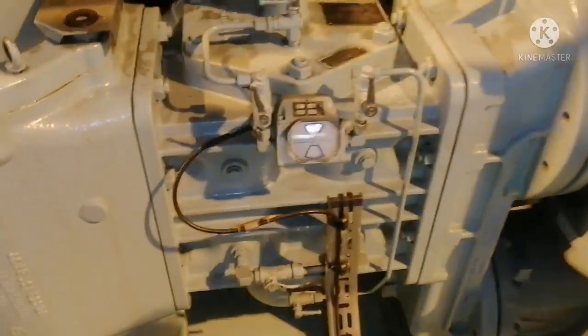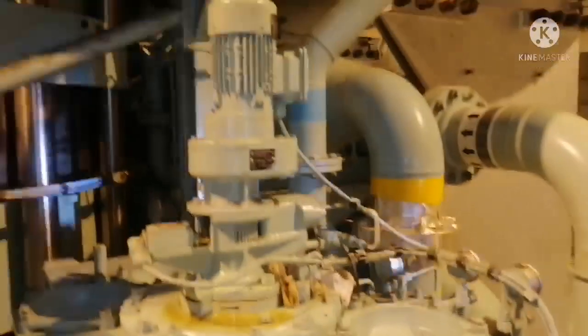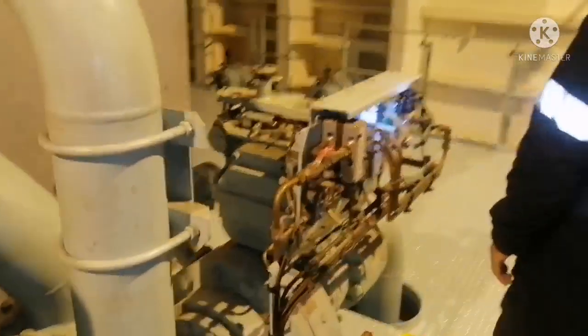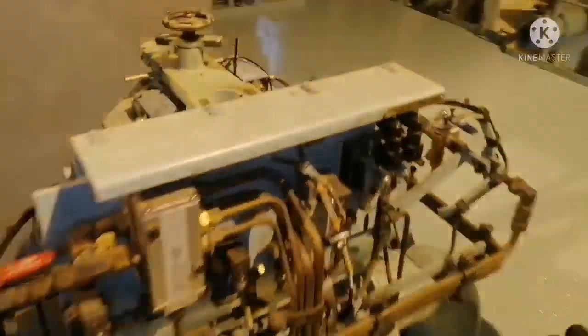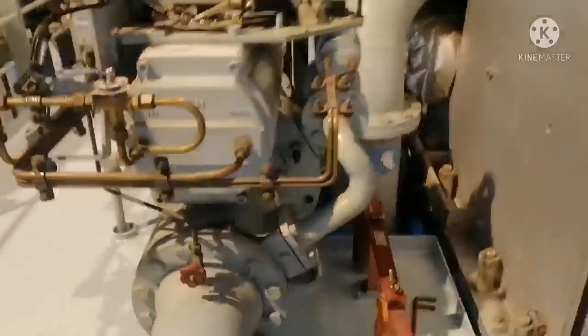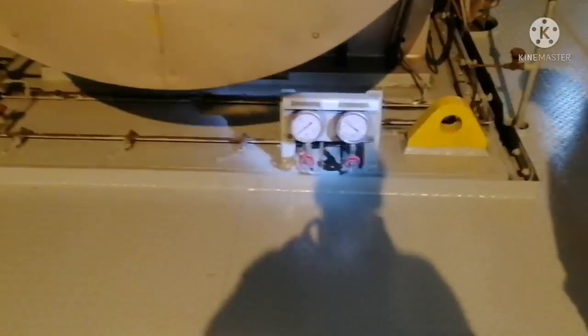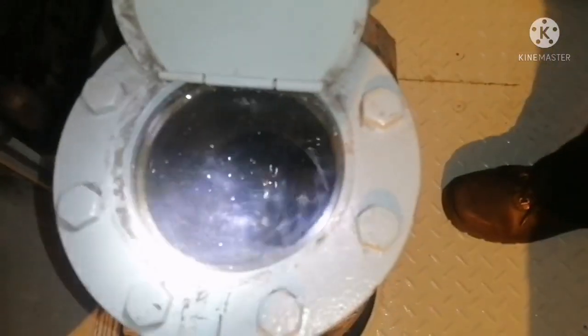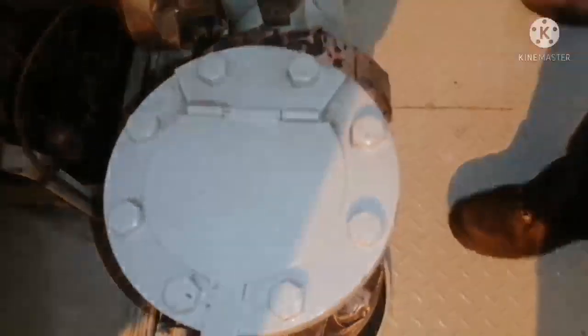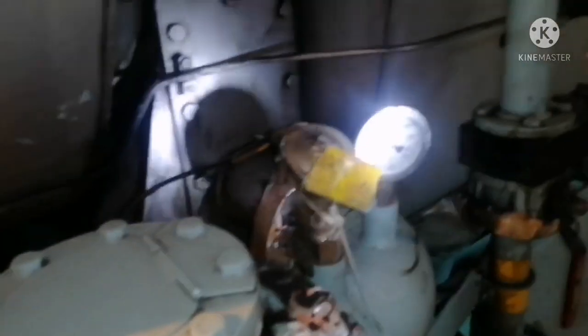This is your lube oil auto filter. Ensure that there is no high pressure alarm, no differential pressure high alarm. This is your starting air valve, the main starting air valve. Ensure that there is no vibration on that. And this is your turbocharger. For the turbocharger, you have to check the lube oil flow in the turbocharger. You have to check the lube oil temperature and the exhaust gas inlet and outlet temperature.